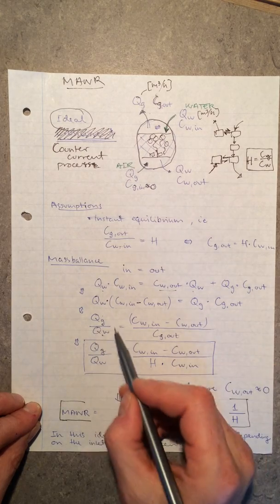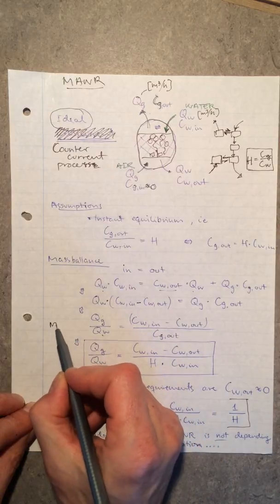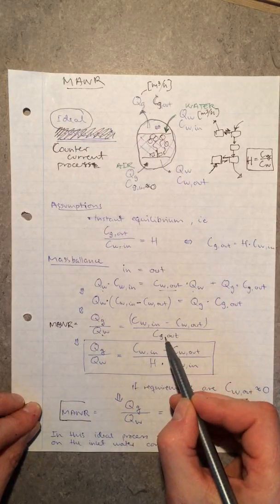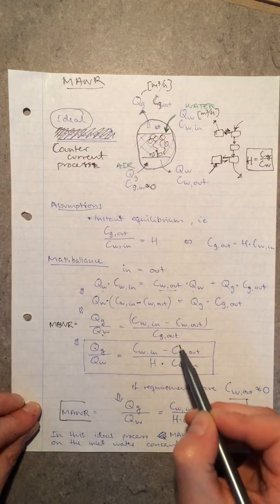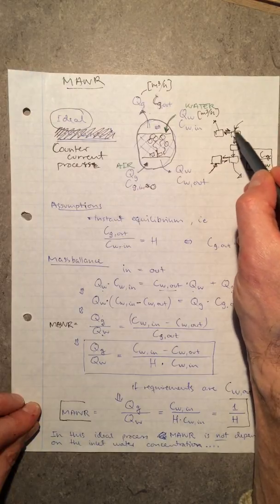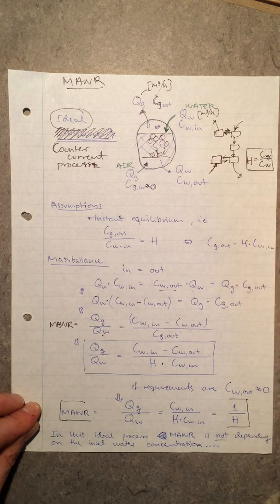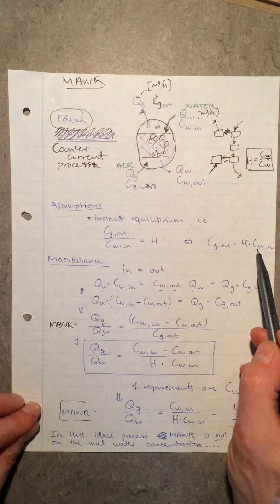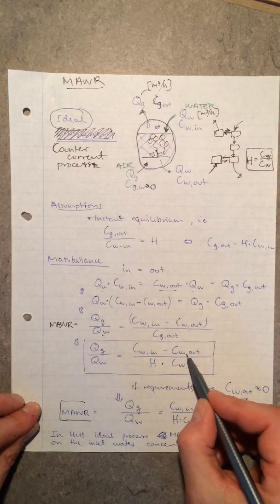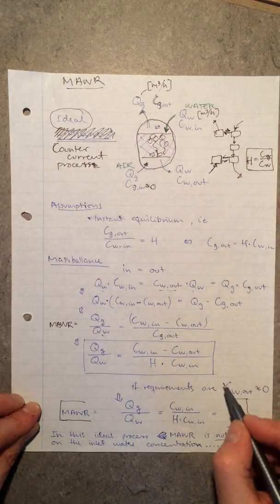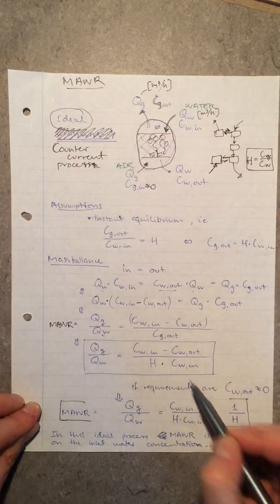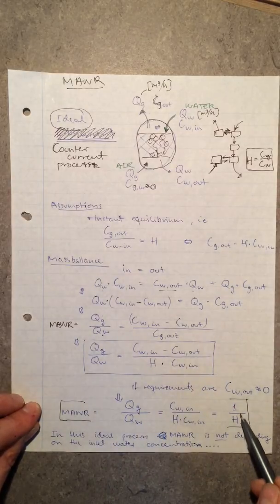I can divide through and get my minimum air-to-water ratio expressed as the concentration of substance in the water coming in minus the concentration going out, divided by the concentration of substance in the gas going out. Now, applying Henry's constant and the equilibrium assumption, I can substitute the gas concentration with Henry's constant times the concentration in the water coming in. If my stripping process is efficient, the concentration in the outgoing water is close to zero, so that term drops out.